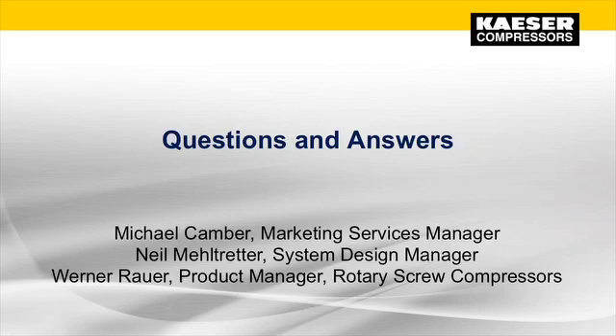Also, if you're noticing any problems with the system, such as inconsistent pressure or higher energy costs, that's a good time to do an audit. The audit can help you find the reasons for those specific problems and help you identify solutions. In general, technologies change over time, whether it be with new master controllers or new controls for compressors themselves. So if you notice that your system is aging, now might be a good time to do an audit. Thanks. Good question.